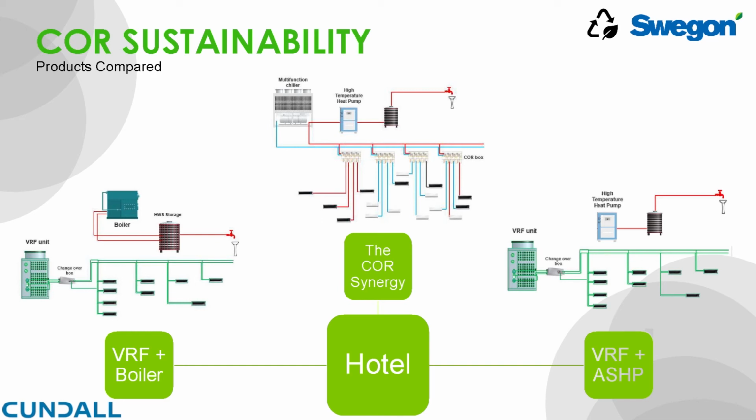The second is the use of refrigerants being restricted, and those that pose a higher risk to the environment are being phased out. For most refrigerants, GWP and flammability are inversely related. Lowering the GWP means that the substance is less stable. This brings the necessity for careful design of fire compartmentation in buildings where low GWP refrigerants are passing through. These two critical factors, together with the flexibility to connect to a future district energy network, make water-based systems, such as the COR, more convenient.